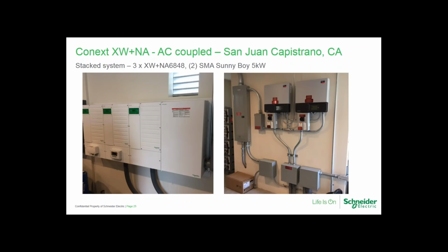Here we see an AC coupled system in San Juan Capistrano. We've got two 5 kW Sunny Boys with a triple XW 6848 system. I don't know if you can see in the picture on the right there in the background, you've got the Unity 2 Deca batteries. This system actually qualified for California's SGIP program and conducted a 2-hour discharge test and got a tidy rebate for that. The Deca Unity 2 batteries actually exceeded my expectations for capacity. So, just a thumbs up for that particular make and model of battery.